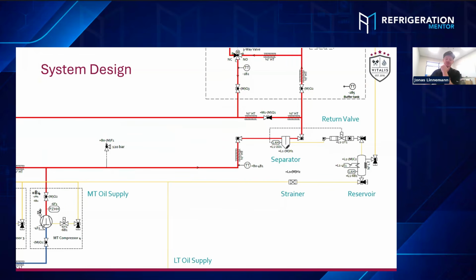So I zoomed in a bit to talk about the oil system we have in the system. You can see the medium temp compressors pushing the whole mass flow through the separator, where most of the oil should be separated. And there's a little level switch at the bottom. As soon as the oil inside the oil separator reaches that level, it activates this little return valve, which is typically a solenoid valve. And this drains in a pretty steady interval, whenever the level is reached, the oil back into the oil reservoir.